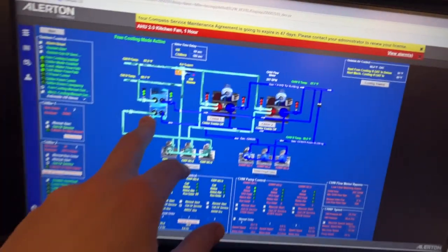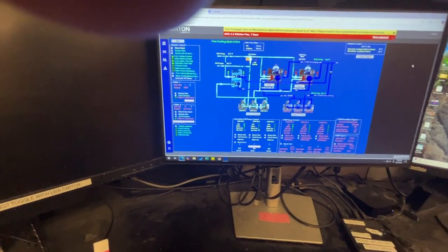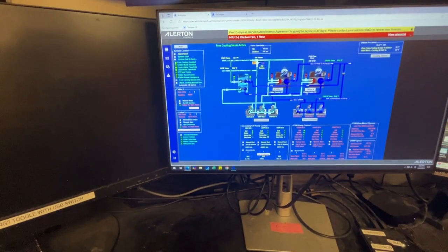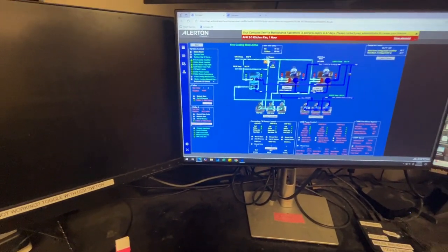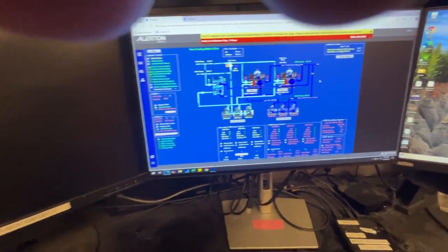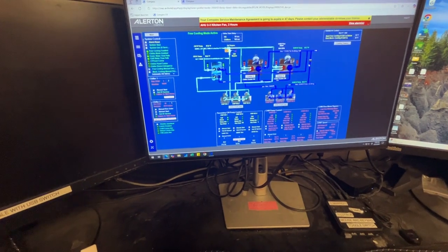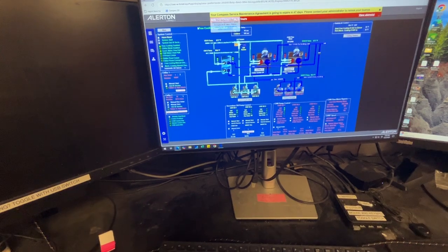So right now it is 60 degrees out, but we're running free cooling right now. Well, it's 4 o'clock. It's about to get cold, so we'll just leave it. I think our high was only 59 today. When we're in between free cooling and mechanical cooling, the building will start to heat up a little bit. But unless we have events, we don't usually run the chiller. We just kind of leave it. Right now we have decent chill water and chill water return temps, so it hasn't heated up too much. It's just a 2-degree delta.